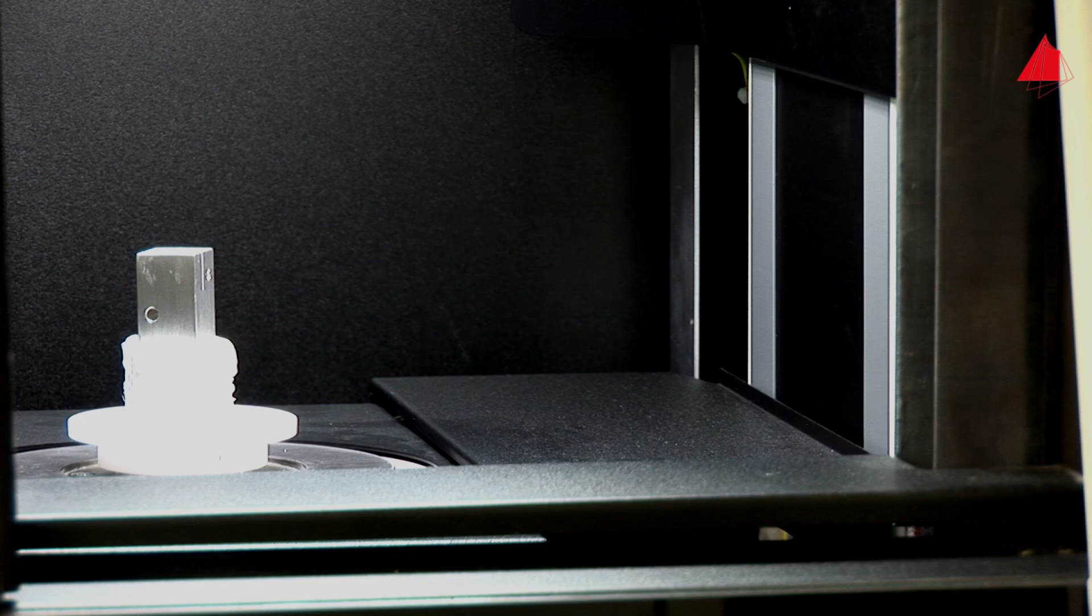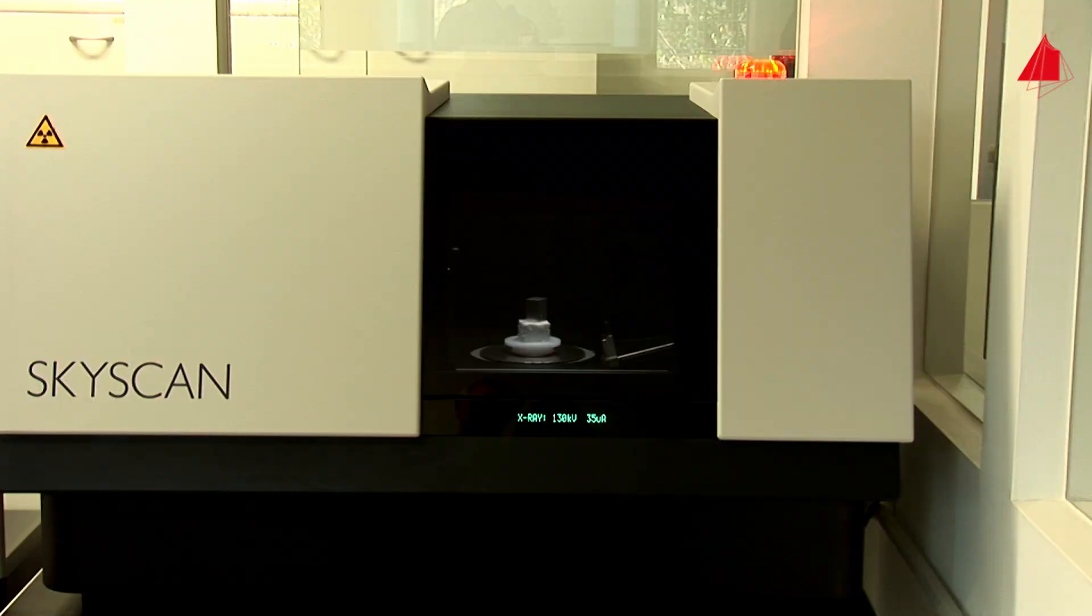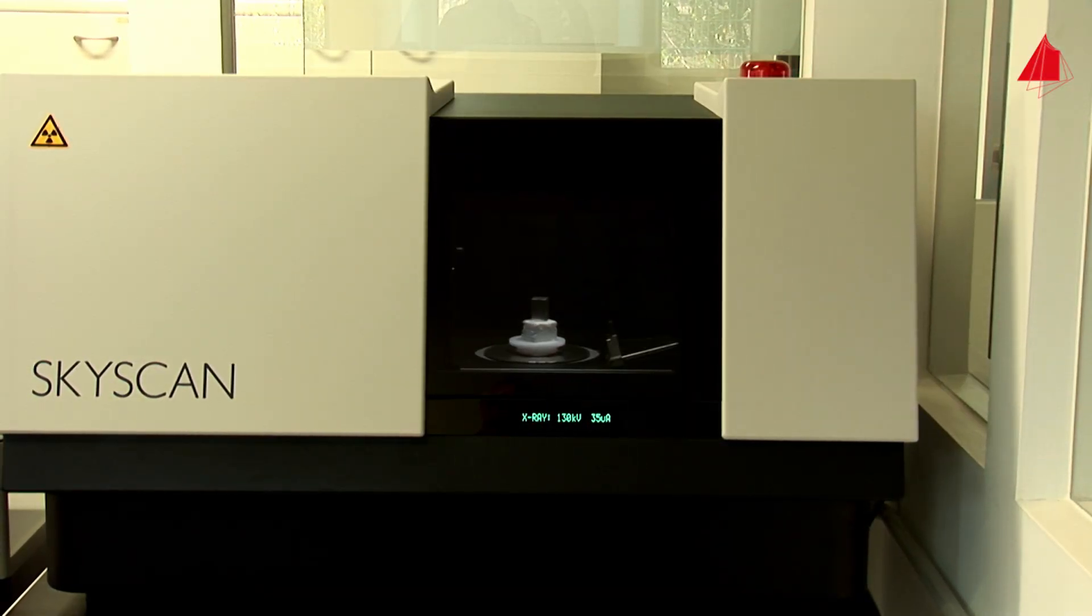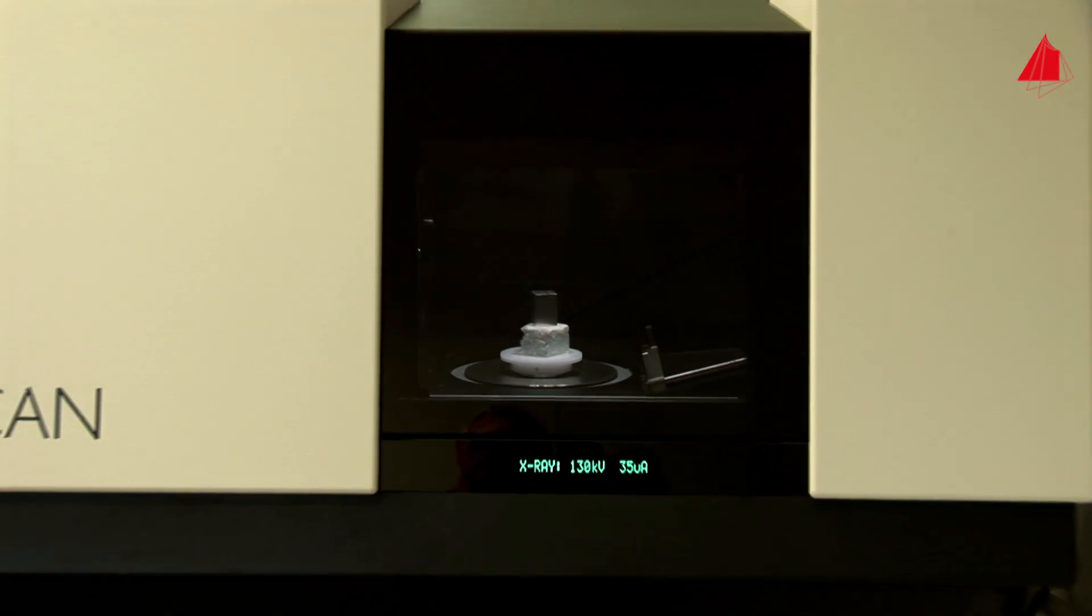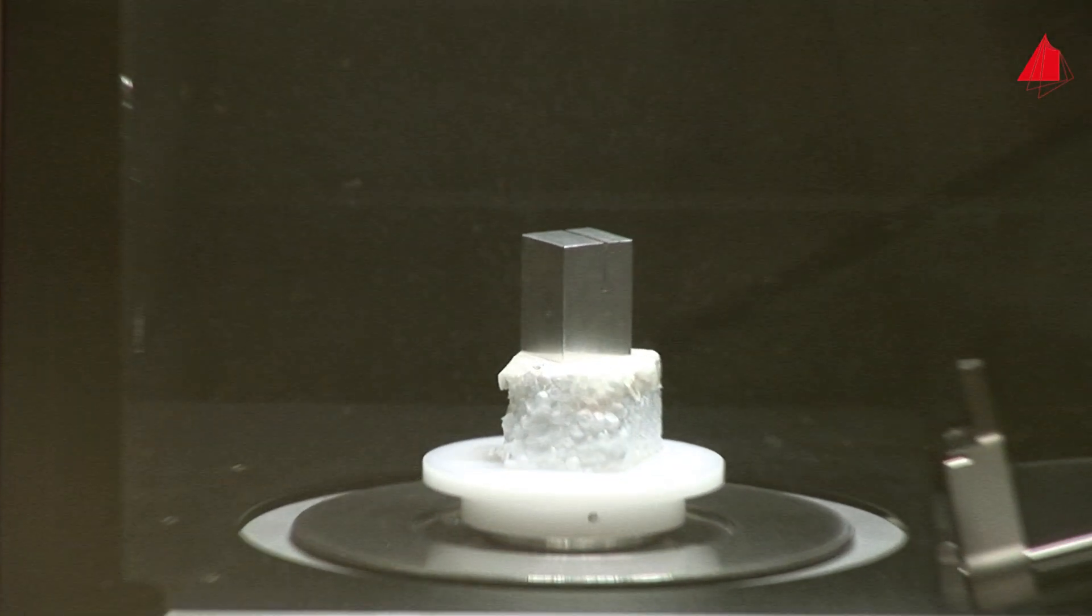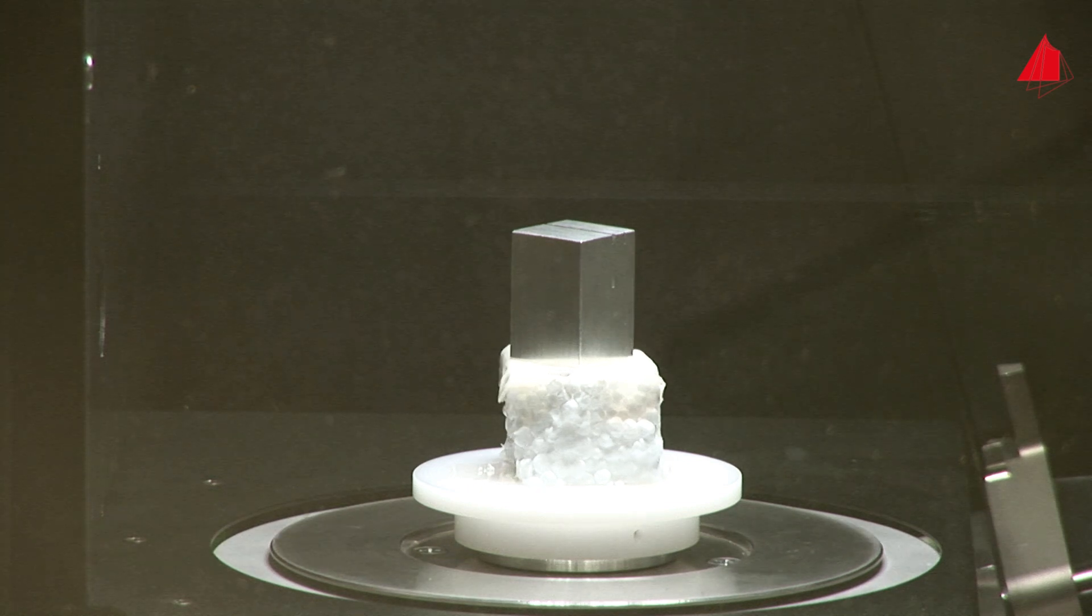The x-ray tube is located on the left side. The detector field is on the right hand side. In step one, the computer tomograph records one x-ray image after the other and saves it. After each recording, the sample stage rotates the specimen by a certain angle. In this way, many individual x-ray images from different directions are captured.